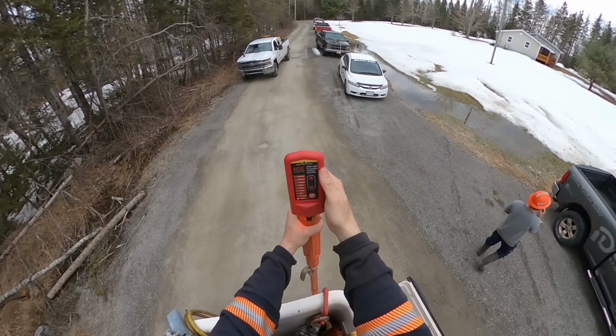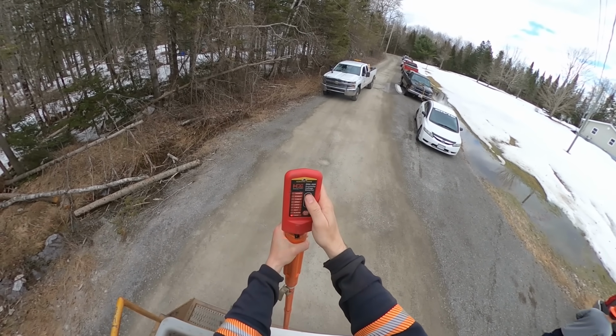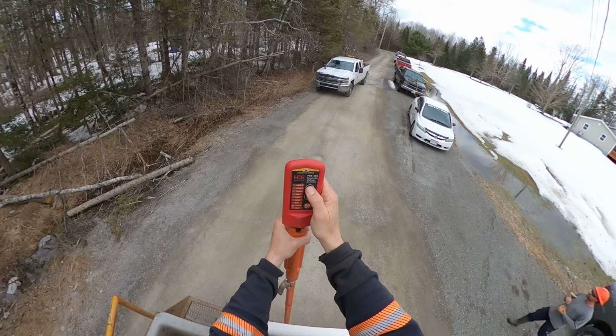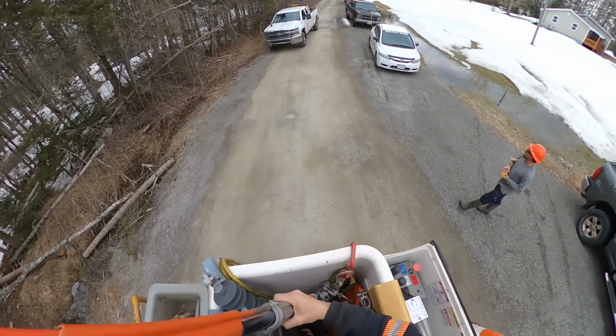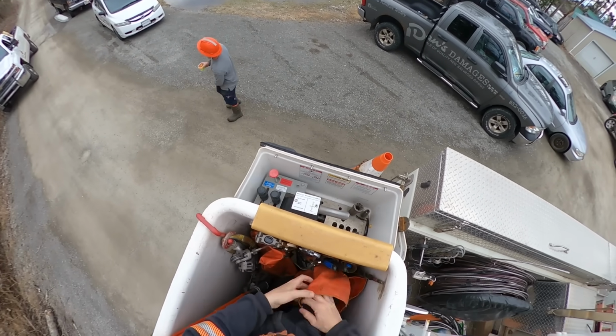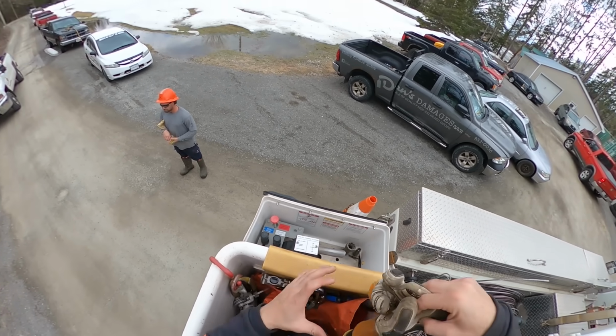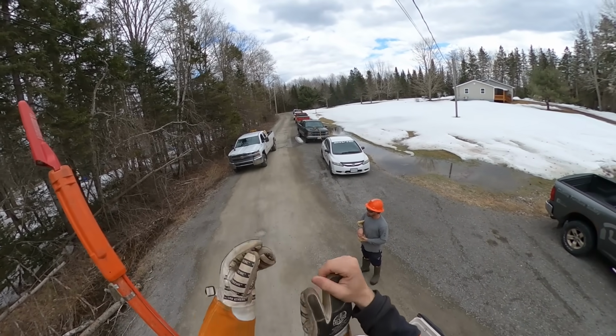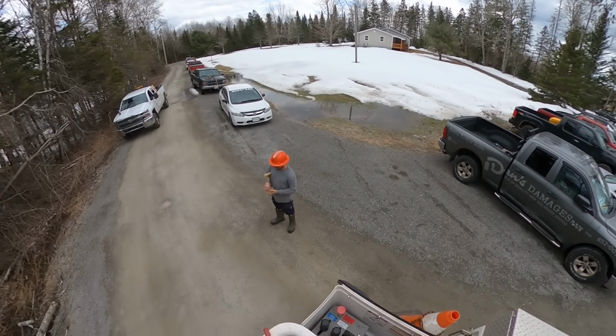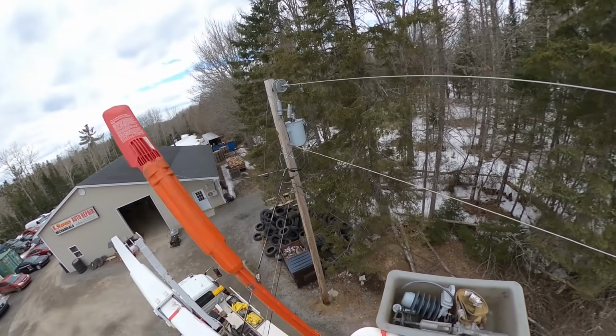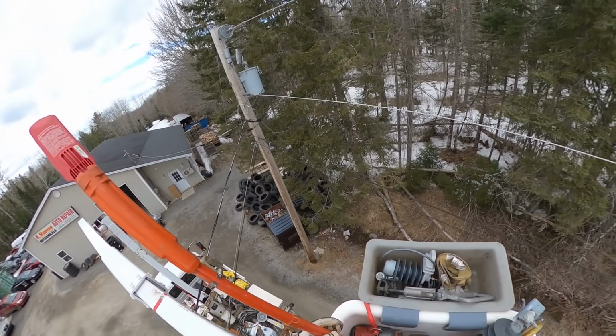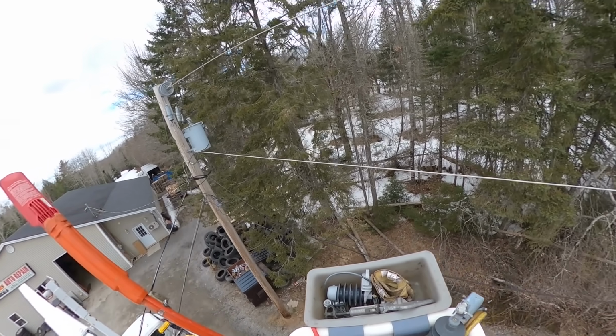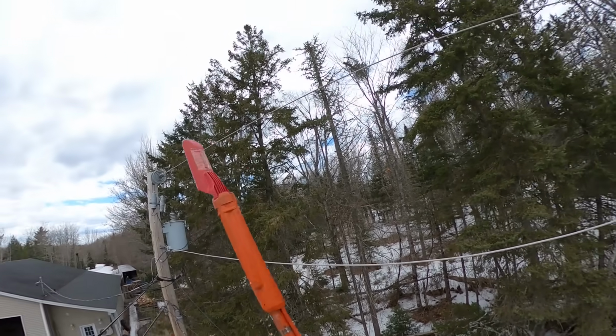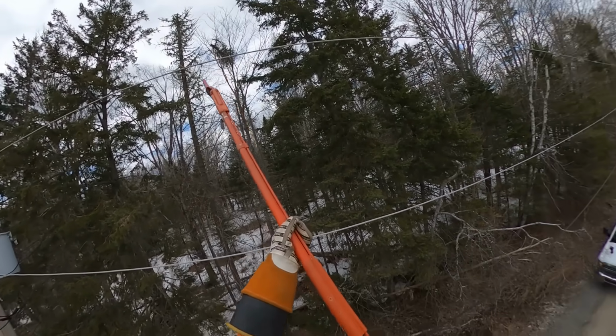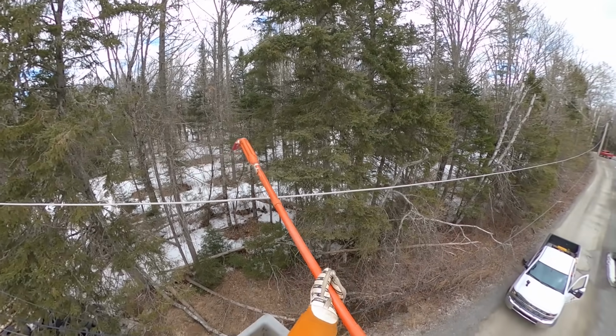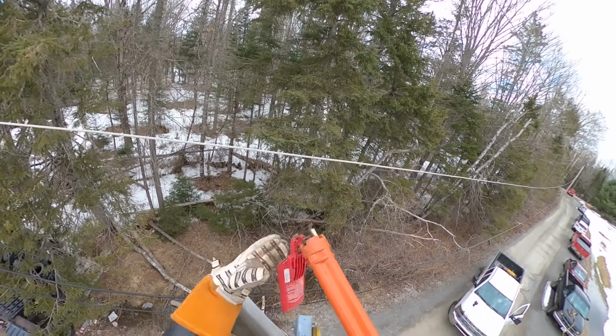So the first step when working on any de-energized lines is to check for potential. Potential meaning voltage. The red attachment on the end of my hot stick is a proximity detector. The setting on it, where it is a 12 kV system, we bring that setting up to the 12 kV mark, even though there's only 7,200 volts on the line itself. So we have this line isolated at the main road. That's the switch set blue at the main road. So our first step here is to check for potential, in which there is none.